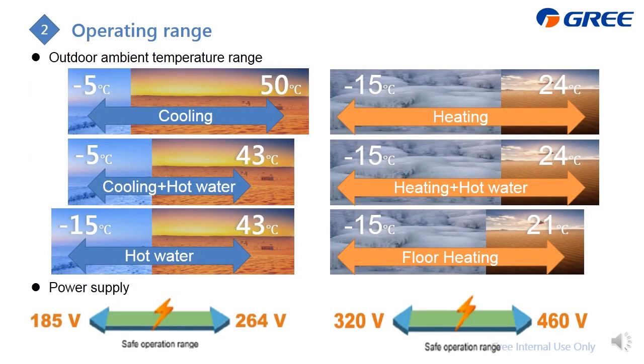For the operating range, according to the mode and the mode combination, we divide it into different ranges. So here for cooling, it is from -5 to 50. Heating is from -15 to 24. And for either cooling or heating plus hot water, the range is a little bit different. If it is only hot water, it's from -15 to 43. If it is floor heating, it changes to -15 to 21. And here is the power supply range for single phase and three phase.